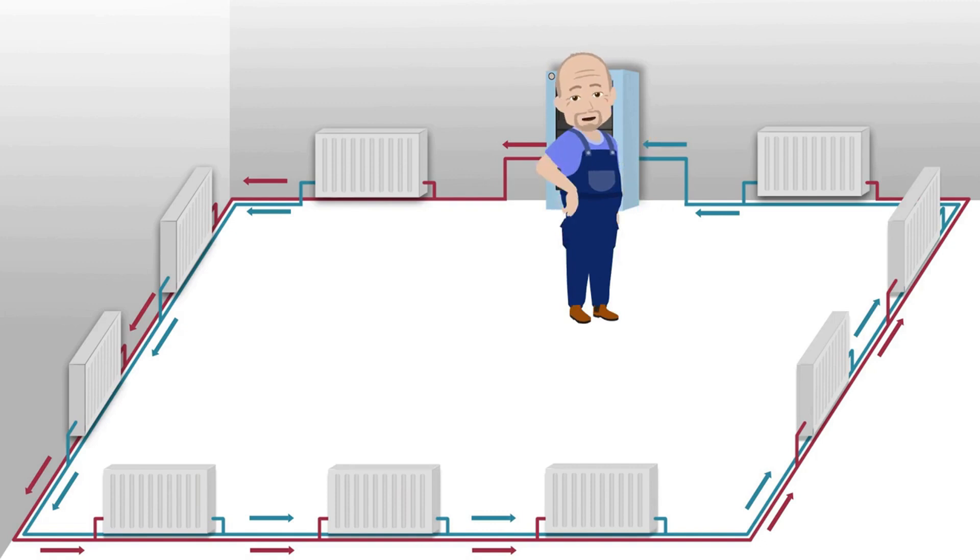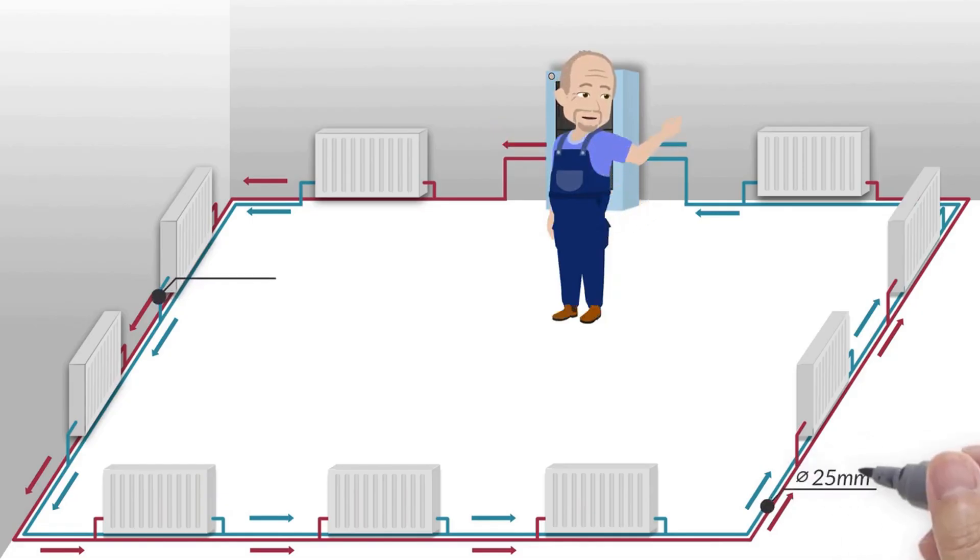But what's most interesting is that the return pipe starts from the last radiator. As a result, an interesting system like this is created. In it, the main supply and return pipes have a diameter of 25 millimeters and the radiator pipes are 20 millimeters.